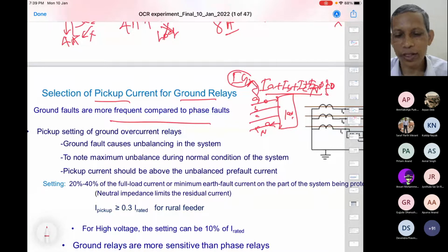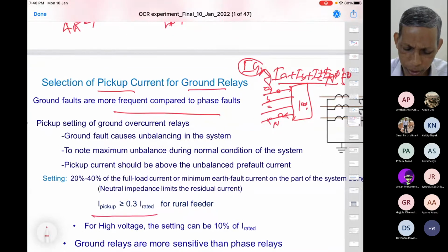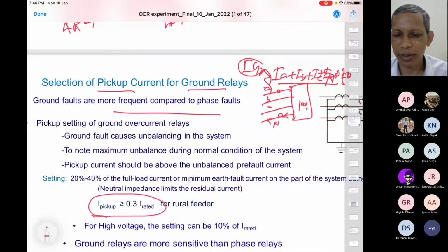So therefore, this is a very sensitive thing. Whenever a ground fault happens, the current will be substantially high, but normally the ground current is pretty low, negligible theoretically. So typically 10 to 20, that's why the pickup current you consider in this case is set to something like 30%, 20%. You can make it smaller also. If your system is very new and reliable, you can make a judgment and make it more sensitive. You can make it not 0.3 but 0.2, 0.1 also, depending upon that.